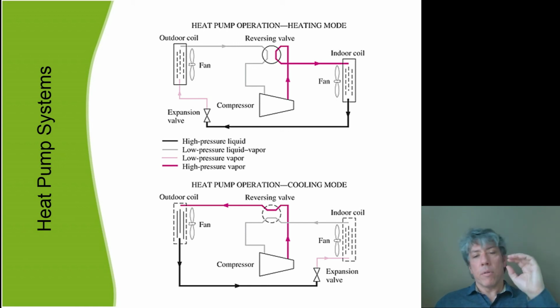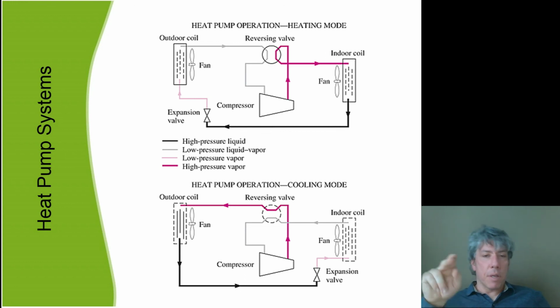Now think about the reverse operation mode, the heat pump operation mode at the top. Notice that all the valve has to do is turn, right? All it has to do is connect the pipes differently. And that's exactly what it does. Now what happens, like what's happening literally right now in my home, is high temperature, high pressure gas refrigerant leaves the compressor and goes directly to the indoor coil. Since it's at a relatively high temperature, what happens is the indoor air cools it down, or another way of saying that is that the indoor air warms up. That's what I need. It's cold outside. I want to warm up my house.